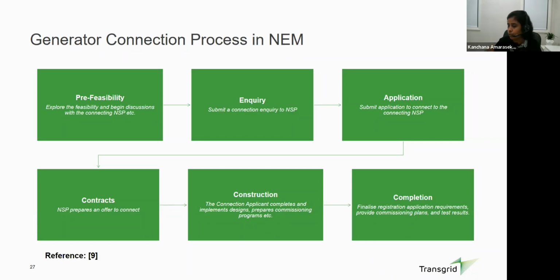So basically they have to overlay the plant performance and the model performance for that stage to be approved. Then we call those stages hold points. And once AEMO and NSP is happy with that hold point testing with the limited generation, they can move on to the next stage. Similarly, they will progress in the commissioning up to the full capacity.